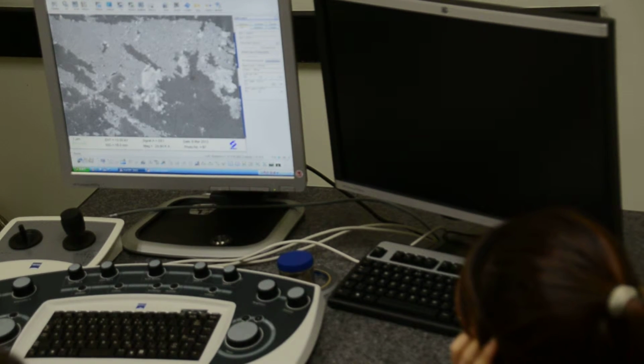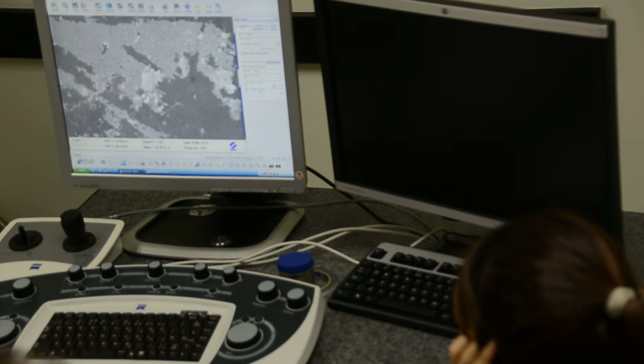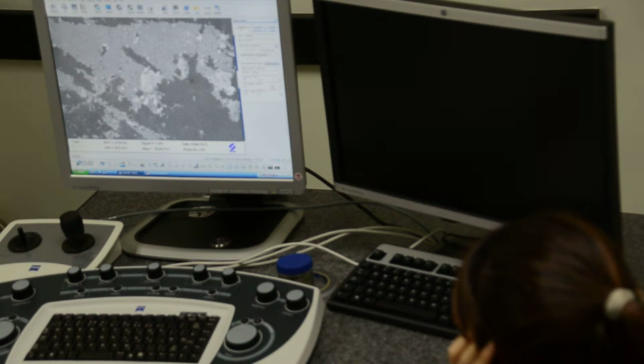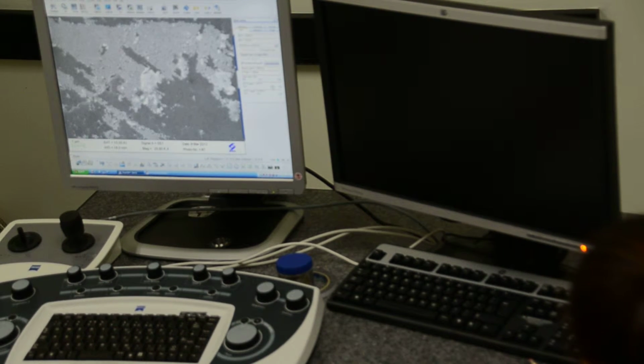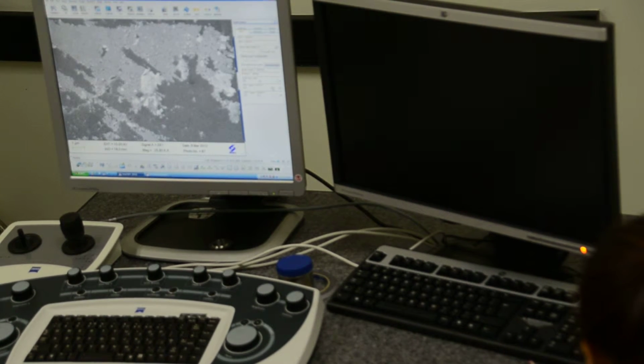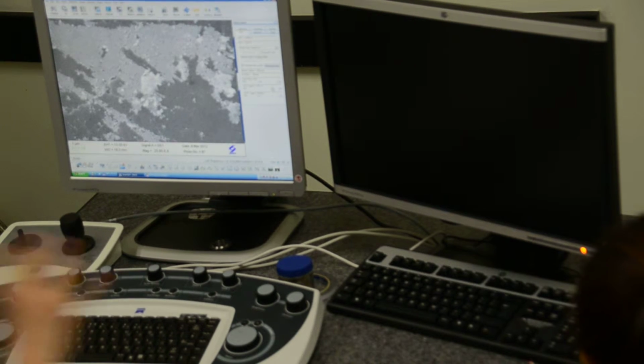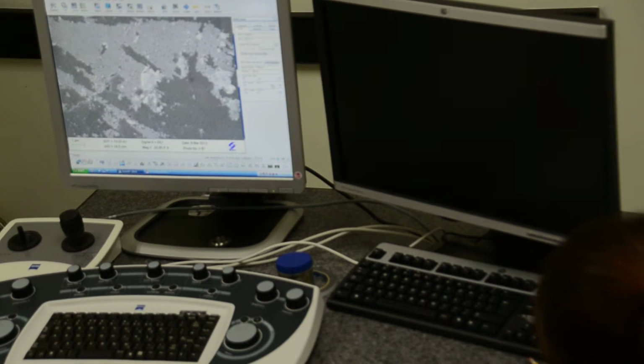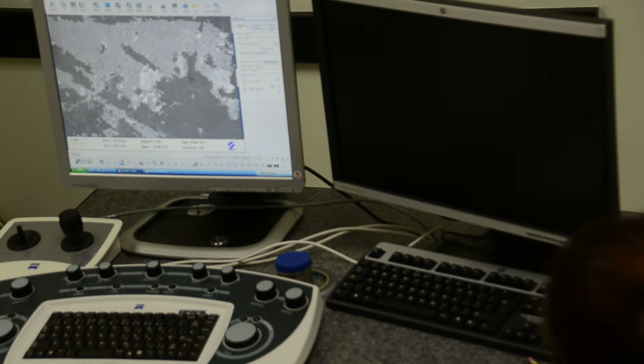Actually your setting is a bit low. You may go to actually already 1. Then you have a bit of saturation. Then you will go to another peak point, about 2.7 ampere. Then the image won't be any sharper or any brighter. So you know this is the saturation point. Saturation point. You look at this point.